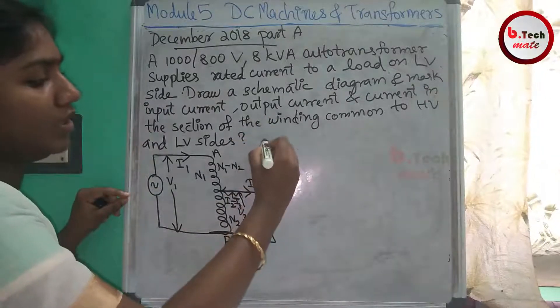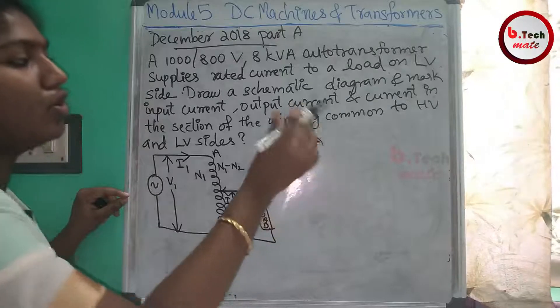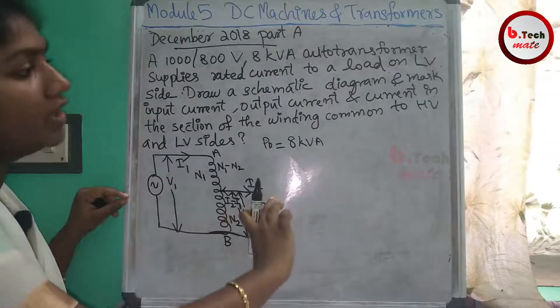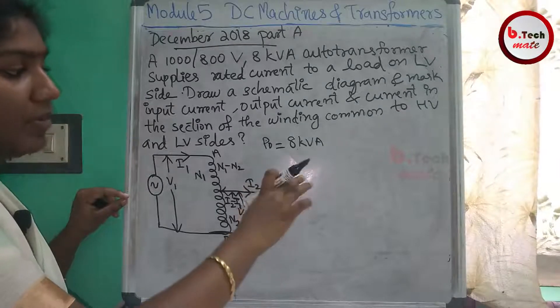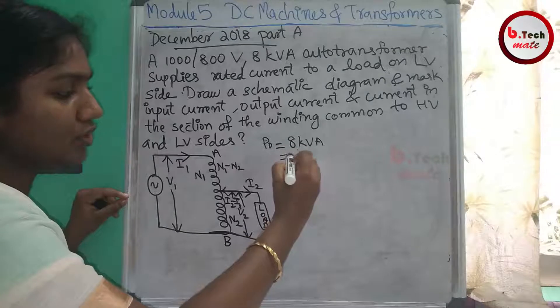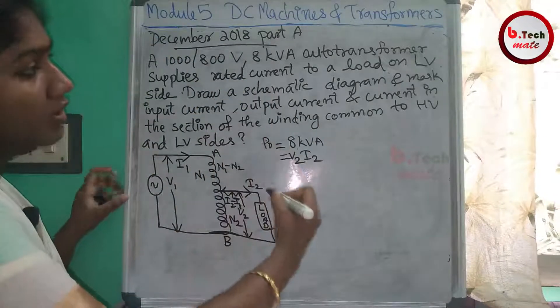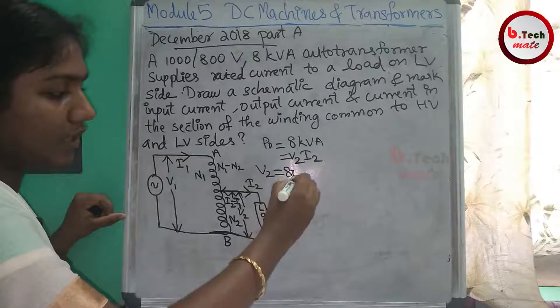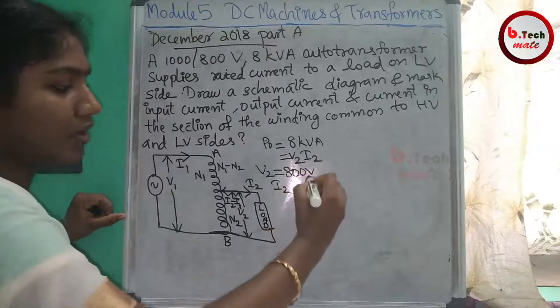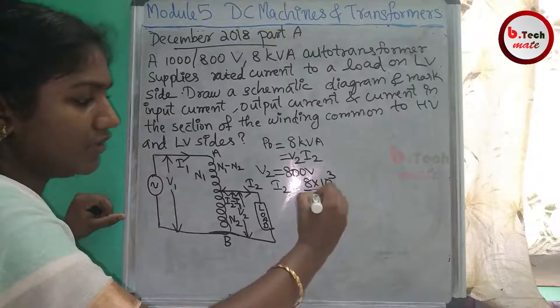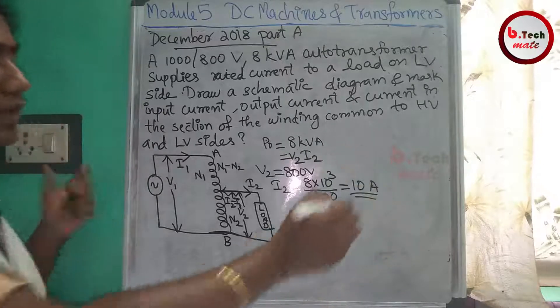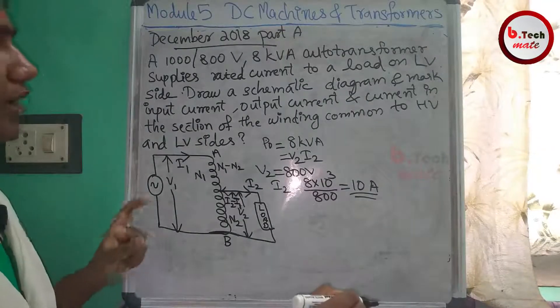The output power is 8 kVA on the load side, so the auto transformer will be loaded on the LV side. Therefore, it will be 8 kVA = V2 × I2. V2 is the LV side voltage, which equals 800V. So I2 = 8000 divided by 800V, which gives us 10A.